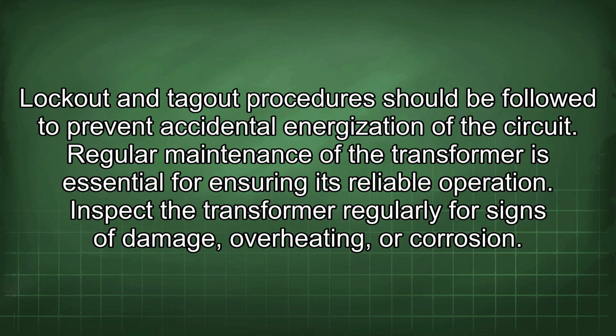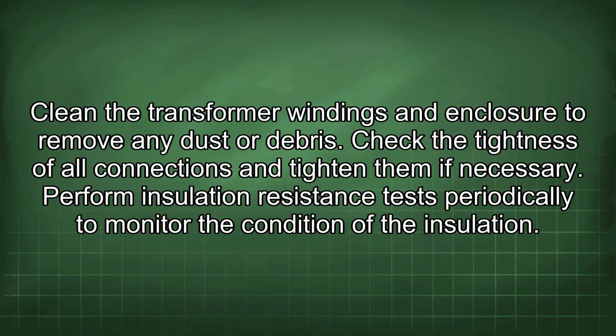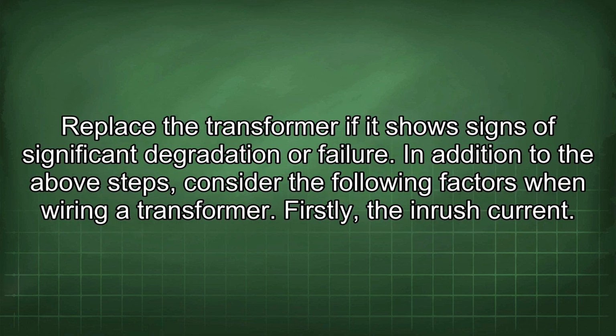Regular maintenance of the transformer is essential for ensuring its reliable operation. Inspect the transformer regularly for signs of damage, overheating, or corrosion. Clean the transformer windings and enclosure to remove any dust or debris. Check the tightness of all connections and tighten them if necessary. Perform insulation resistance tests periodically to monitor the condition of the insulation. Replace the transformer if it shows signs of significant degradation or failure.